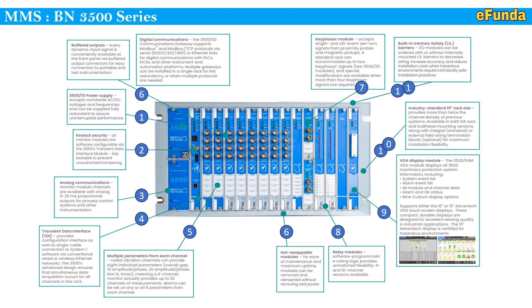Tenth — intrinsically safe barrier I/O modules can be ordered with or without internally mounted IS barriers to decrease wiring, increase accuracy, and reduce installation cost when the hazardous environment requires intrinsically safe installation practices. Data communication is also part of this system.